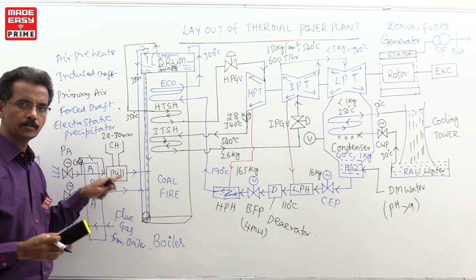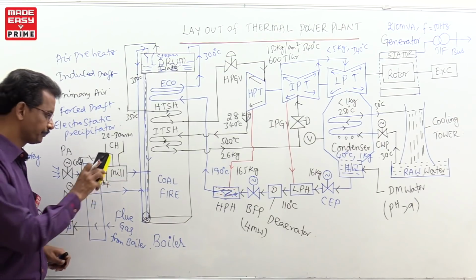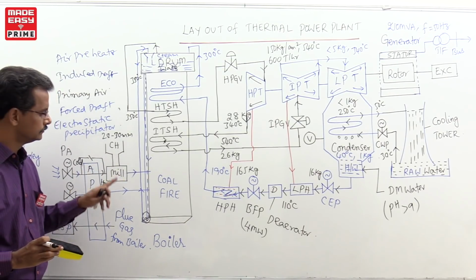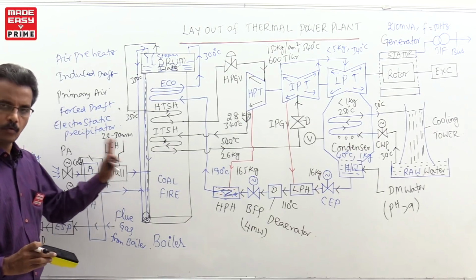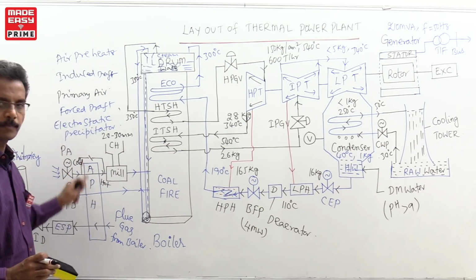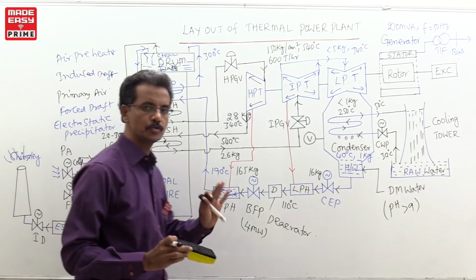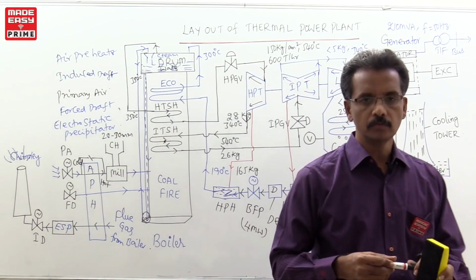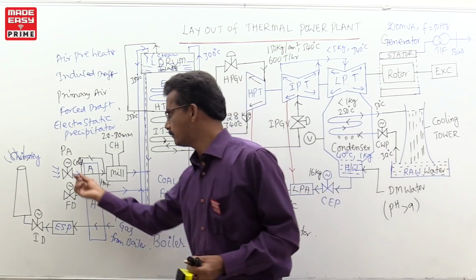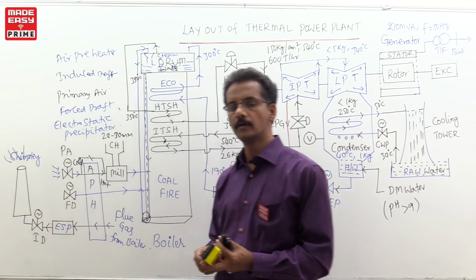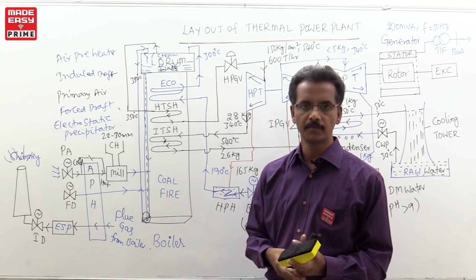After that, it is passed into the mill, where it is used to remove the moisture inside the coal. That is the functioning of this air preheater. The air preheater is used to increase the temperature of the primary air and FD fan air, so that it finally improves the thermal efficiency.